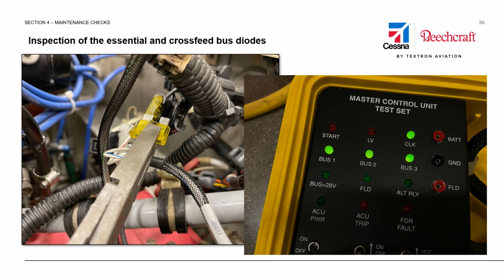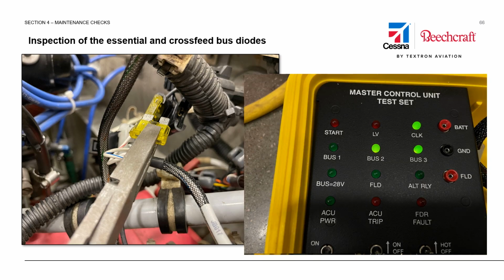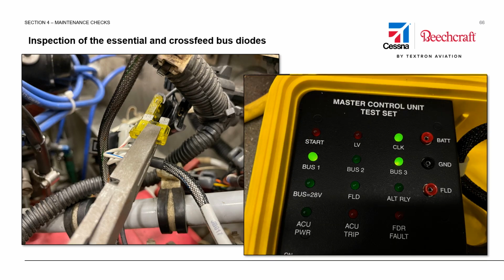If you still have that Lamar TE-04 test set installed from doing the overvoltage check, you can use this to your advantage for the diode check. Instead of pulling leads from breaker terminals, you can simply pull the inline fuses to take the individual buses offline. Verify the appropriate bus lamp extinguishes on the TE-04 and do the same checks with the lights and the GEA. Don't put away that TE-04 quite yet. We'll talk about that more in the next video as well.